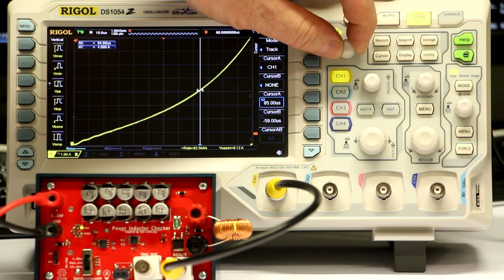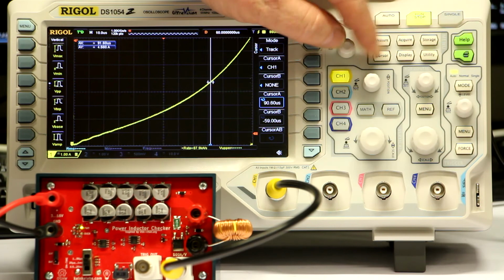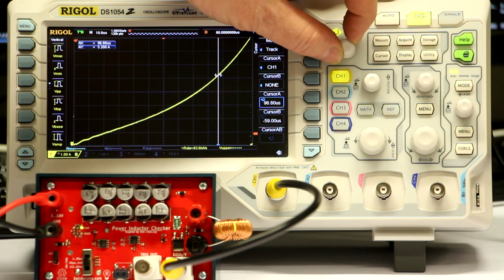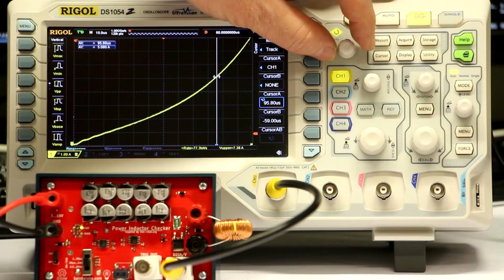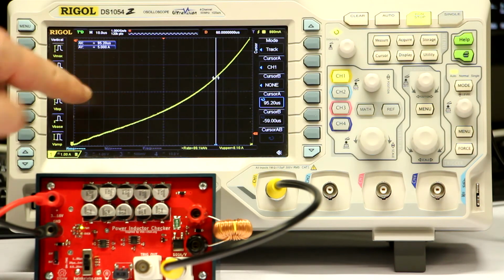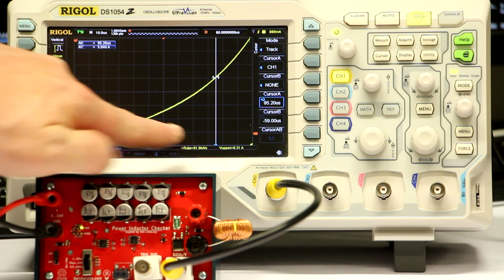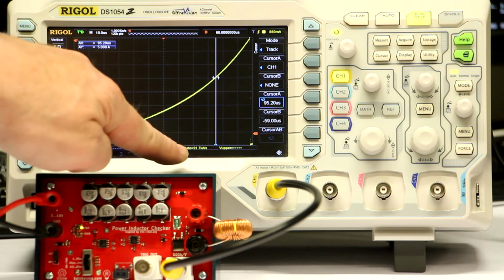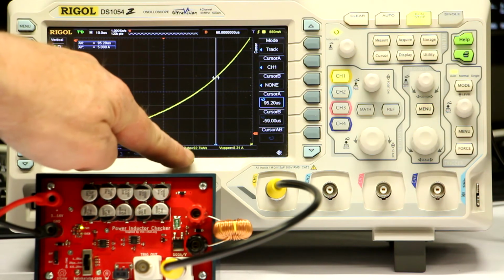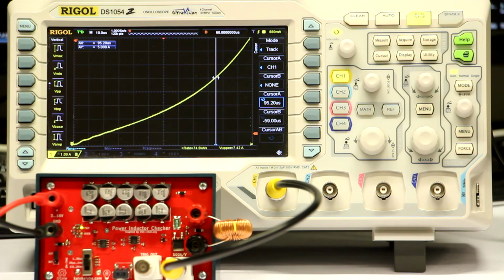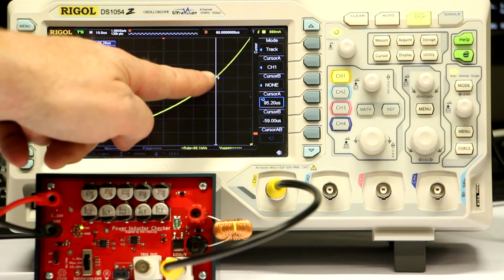So let's tweak around a bit, and here we are at exactly, more or less exactly, 5 amps. And now the rate, the total slope here has changed a little bit, jumping around a bit, to around 90 kiloamps per second. And this is the slope measured from the initial point, 0 microseconds and 0 amps, up to 5 amps.